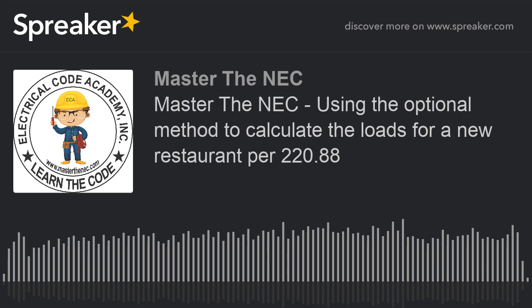Now, let's get on to the table. What you've got here is Table 220.88, which is an optional method. It's a permitted load calculation in lieu of Part 3. And this is for service and feeder conductors for new restaurants. Okay? So you've got 3 columns here. You've got total connected load, you've got all electric restaurant calculated loads, and you've got not all electric restaurant calculated loads.